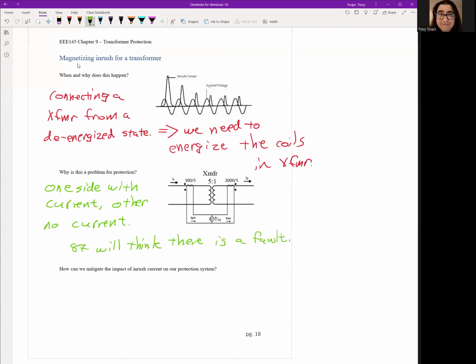Okay. Not only is the inrush current only on one side, it tends to be higher than your load current, so it's kind of a double whammy. So here we're gonna have some inrush current coming in from one side, most likely the high voltage side, because that's the source side, and a current going out on the other side is 0 amps. So again, if it wasn't for inrush and those normal operations, you would assume high current on one side, 0 on the other. It's an internal fault, so the 87 would trip.